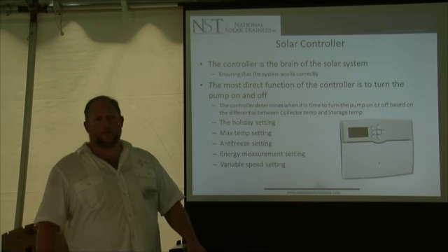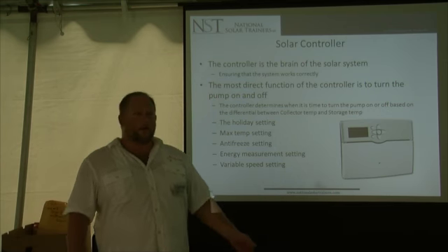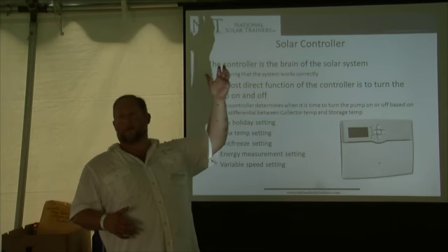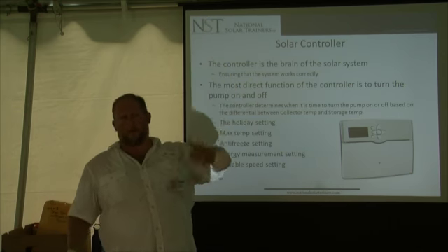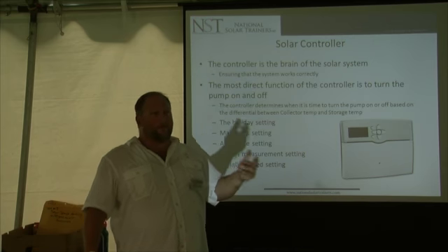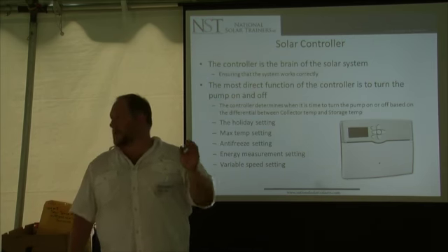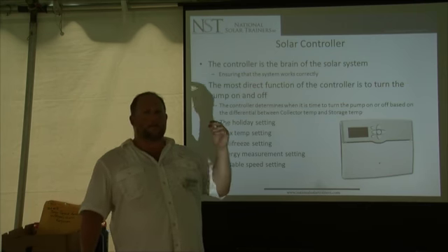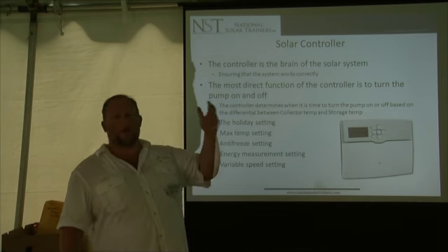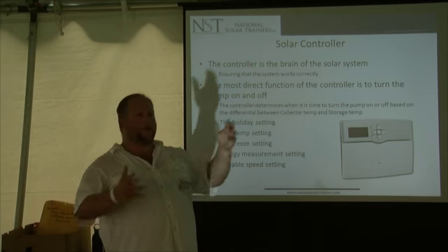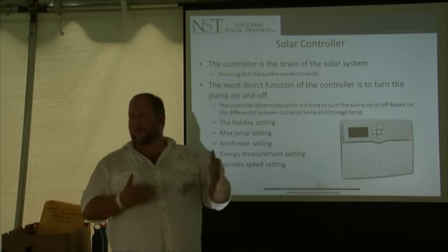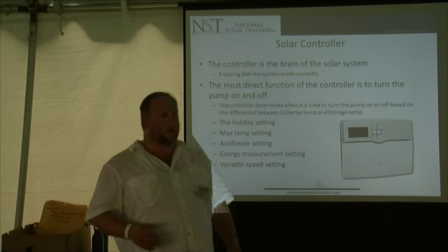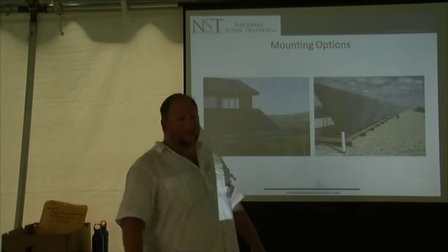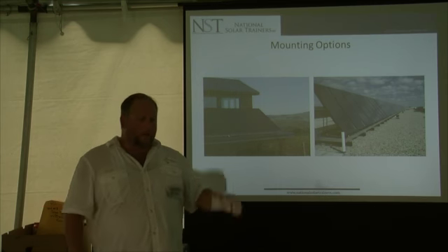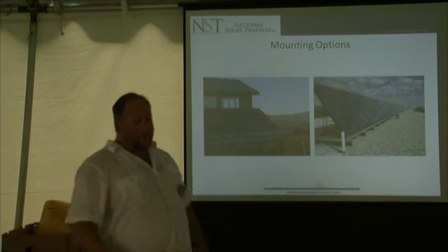The controllers these days are pretty user-friendly. Basically, they look at the temperature of the collectors compared to the tank, turn the pump on. But they can also regulate the velocity of the pump. And it's not just 100%. Okay, it's going to run at 30% or 70%. Whatever is coming in as insolation, the pump will respond according to the controller. All right. There's also data logging capabilities. Mounting, tilt mount. Go over this.